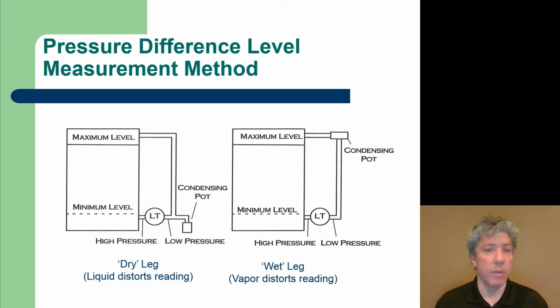The LT is a level transmitter, and what that means is it takes the level measurement and transmits it to a controller. And what you'll notice is that the leg on the left side goes from the area above the liquid that says maximum level. Okay, that area, really the maximum level is that line at the top, and the tubing there attaches to the gas above the liquid.